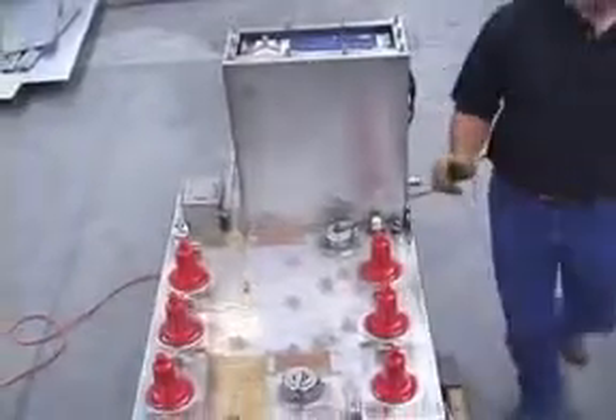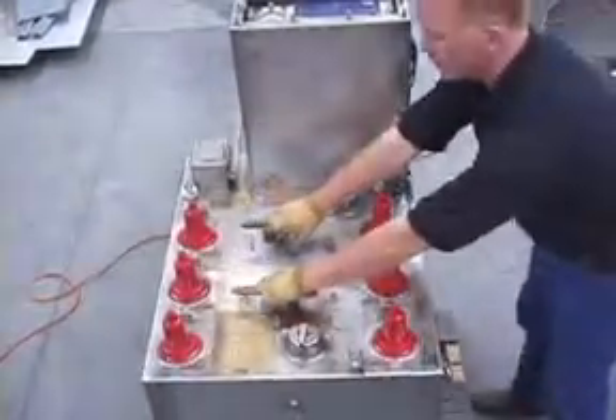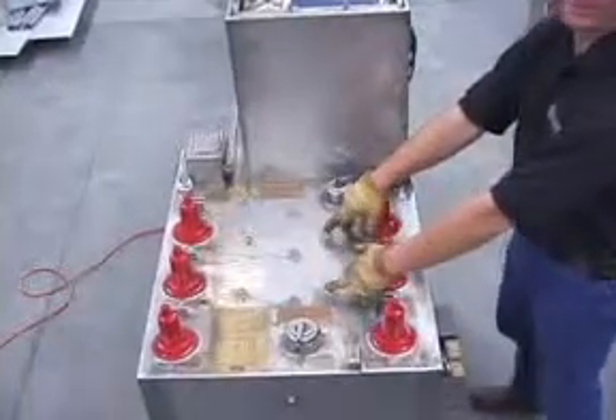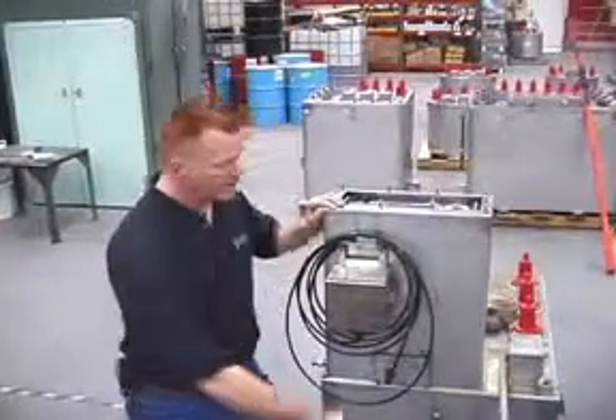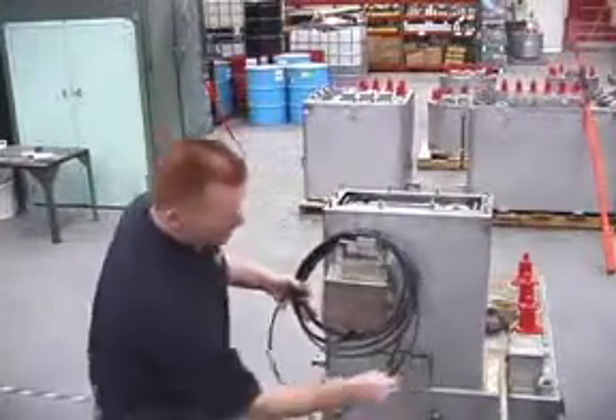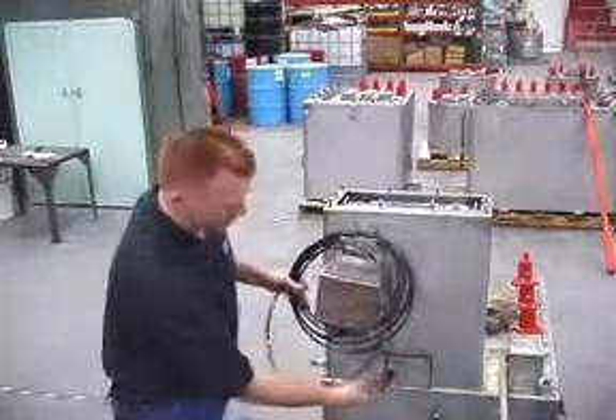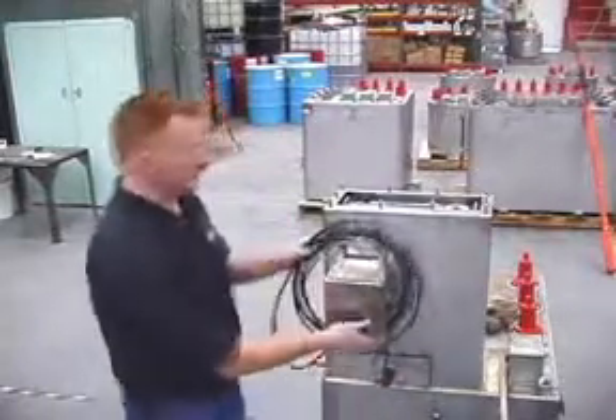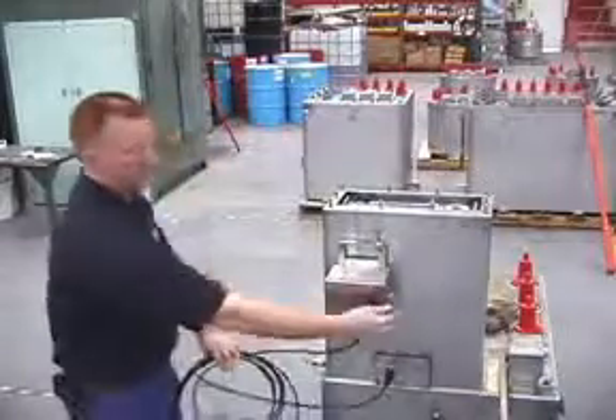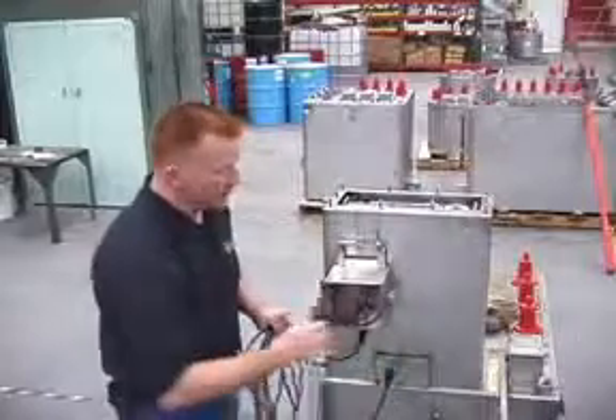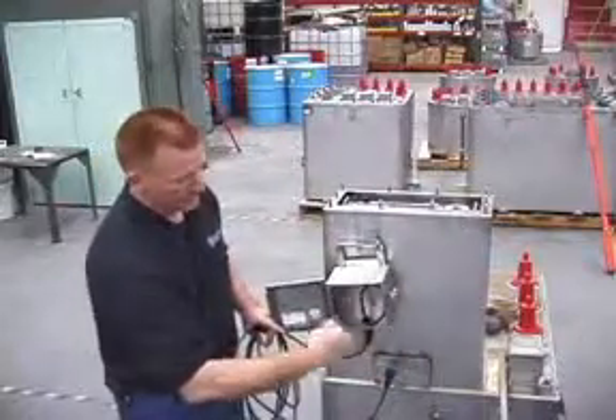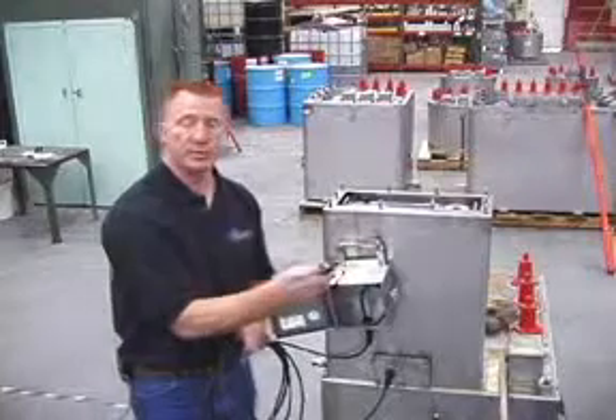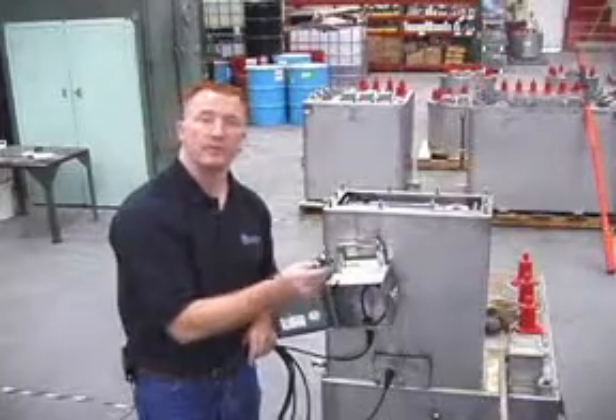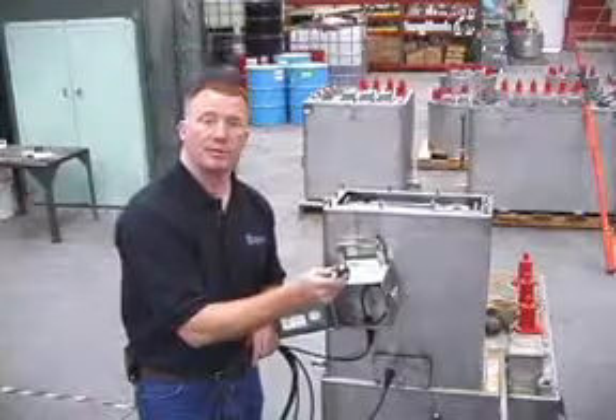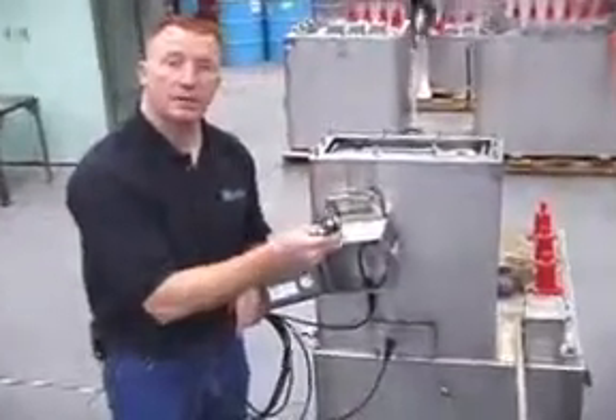The unit is easily motor operated. It comes with the studs mounted on the roof for an easy retrofit of a motor operator. Now here, from the back side of the unit, you can see the fiber optic cord exiting the back of the control cabinet, and the watertight stainless box that contains the fiber optic converter to an RS-232 port so that the field engineers can hook up their laptop computer at grade level without having to climb down into the manhole.